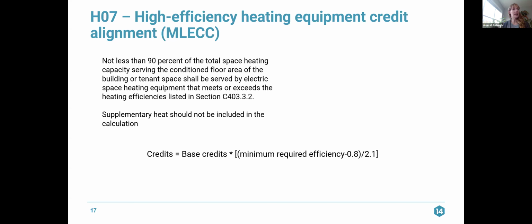But the way that this will be calculated is you'll take the base credits from the tables in the model low energy and carbon code, multiply them by the minimum required efficiency in section C403.3.2, subtract 0.8 from that and divide it by 2.1. And you can do that for each type of HVAC equipment that you have in the building that achieves this requirement. But again, they must be electric. Any natural gas wouldn't achieve these credits.